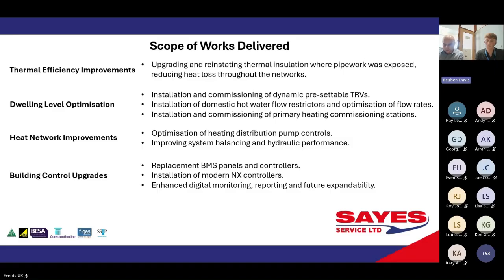We also carried out substantial building controls upgrades, replacing the heating controls equipment and installing modern web-enabled NX controllers. This provides Connect Housing with a much more capable and expandable controls platform, along with enhanced visibility of system operation and performance. Importantly, these measures weren't delivered in isolation - each improvement was designed to complement the others, creating a more efficient, controllable and better performing heating system as a whole. Next slide, please.